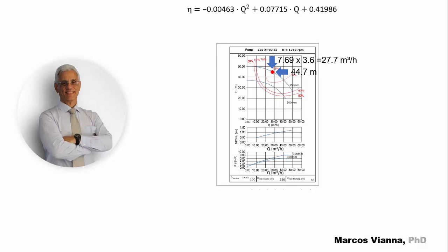We know the efficiency equation for this impeller, so we can calculate its value at the operating point, which is equal to 0.74 or 74%. Also, we know the BHP equation for this impeller, so we can calculate its value at the operating point, which is equal to 6.40 HP. Finally, we know the required NPSH equation for this impeller, so we can calculate its value at the operating point, which is equal to 0.83 meters.